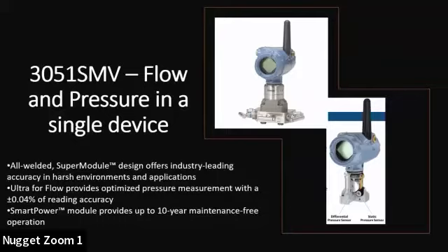The power modules are lithium and they are not rechargeable, but we do estimate on a 1 minute update rate, depending upon the temperature and what have you, you should get about 5 to 10 years out of each module, in which case you would replace it. There are a few other parameters in there, which I'm not going to go into in detail, but I'm happy to answer your questions later.